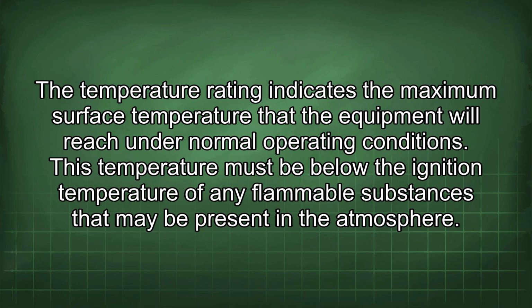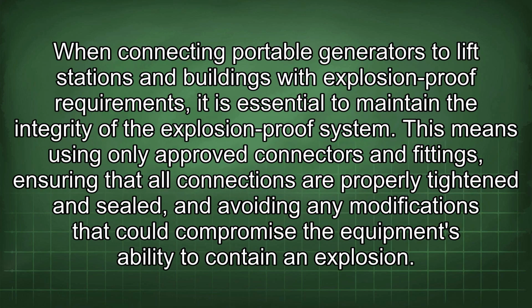This temperature must be below the ignition temperature of any flammable substances that may be present in the atmosphere. When connecting portable generators to lift stations and buildings with explosion-proof requirements, it is essential to maintain the integrity of the explosion-proof system. This means using only approved connectors and fittings, ensuring that all connections are properly tightened and sealed, and avoiding any modifications that could compromise the equipment's ability to contain an explosion.